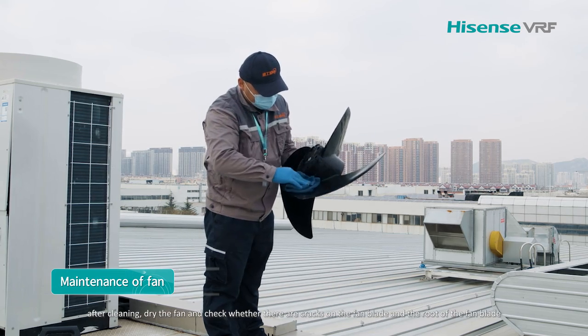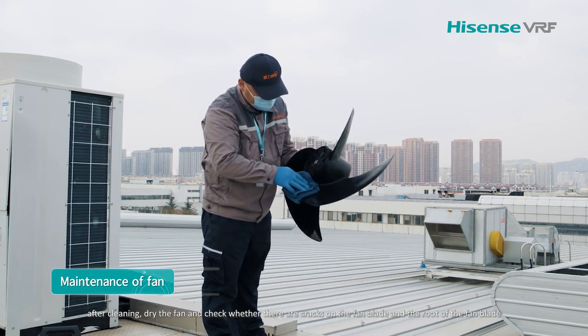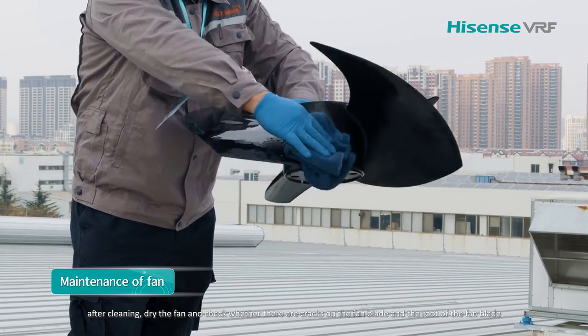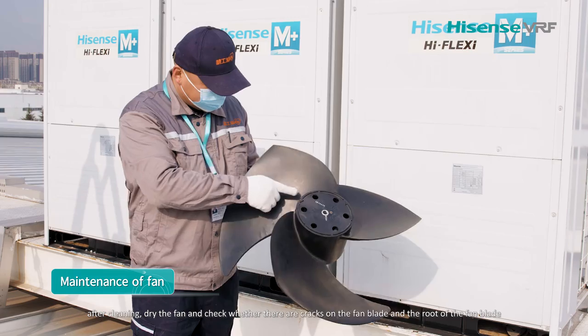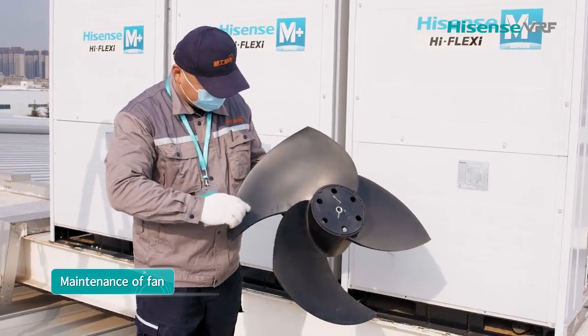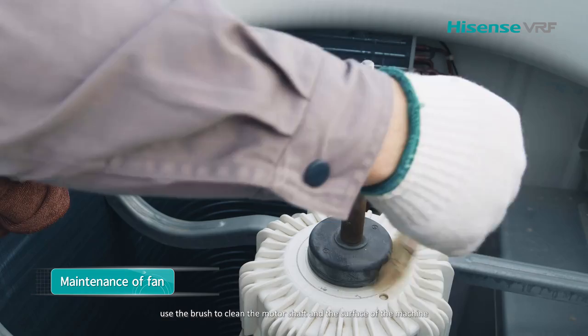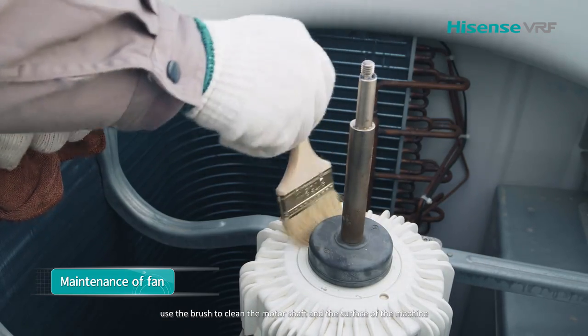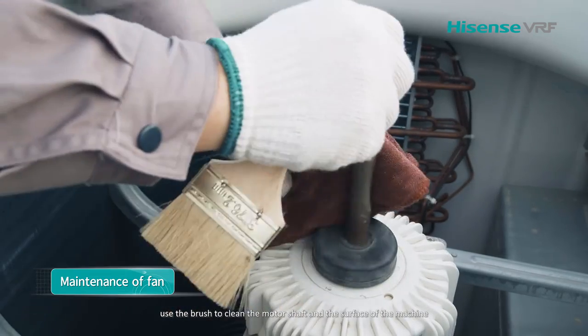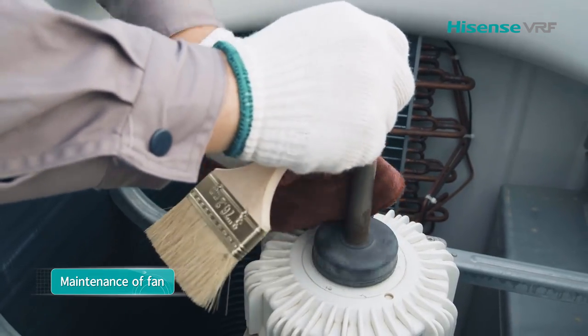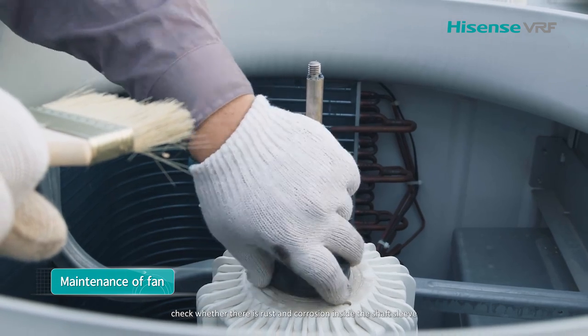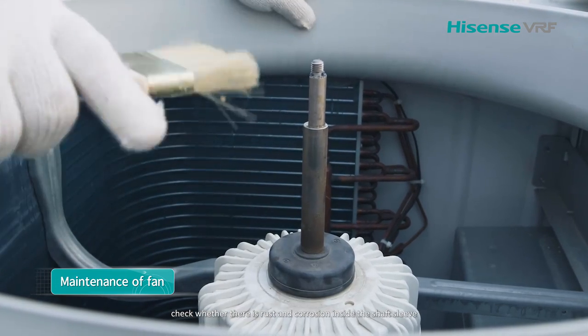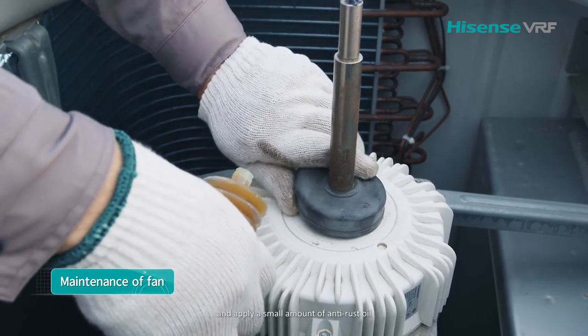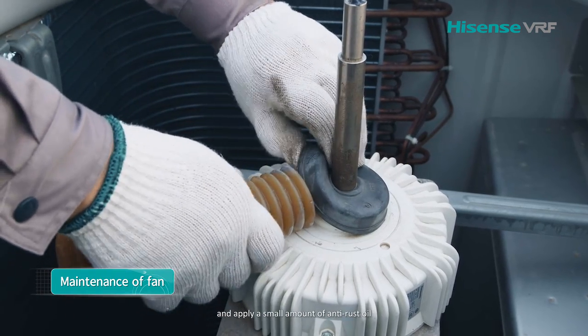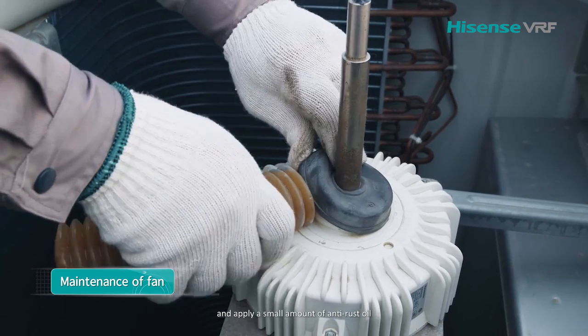After cleaning, dry the fan and check whether there are cracks on the fan blade and the root of the fan blade. Use the brush to clean the motor shaft and the surface of the machine. Check whether there is rust and corrosion inside the shaft sleeve and apply a small amount of anti-rust oil.